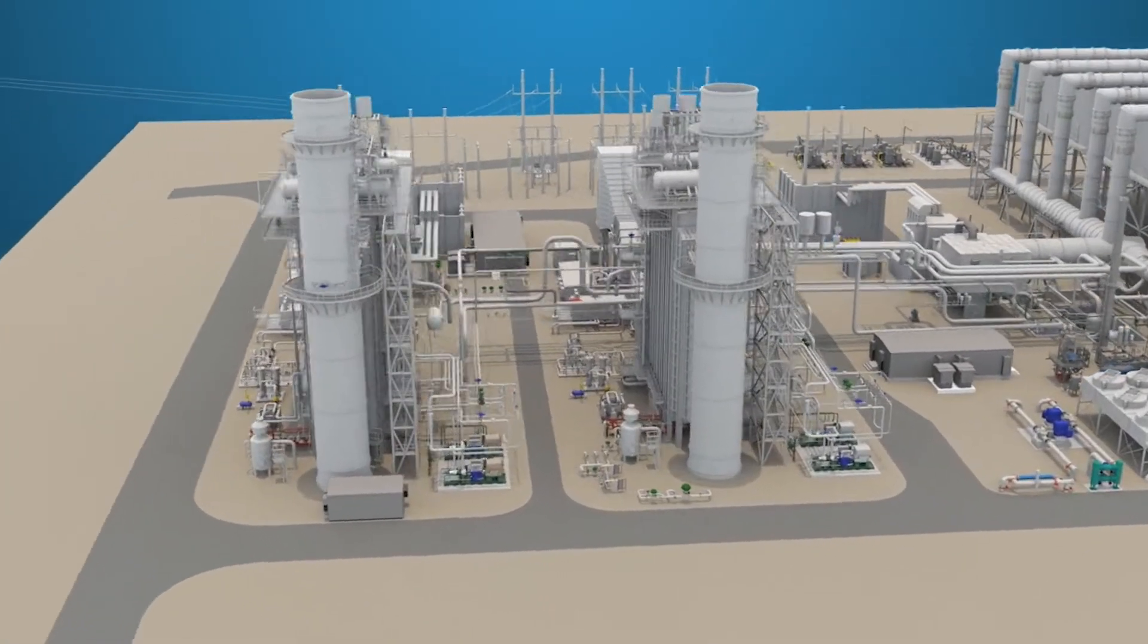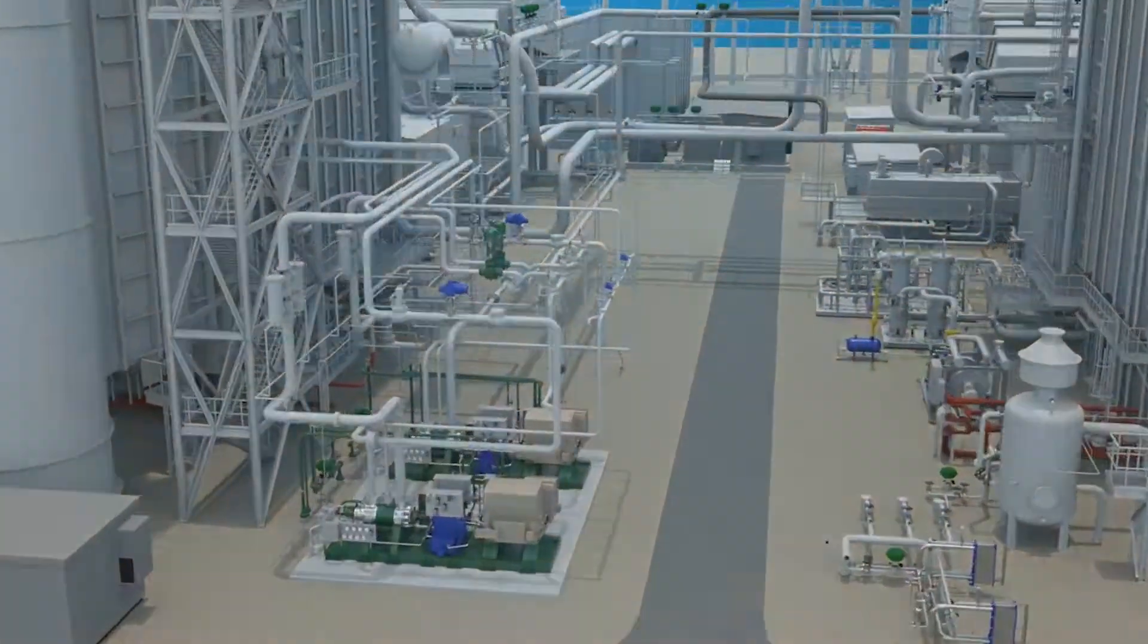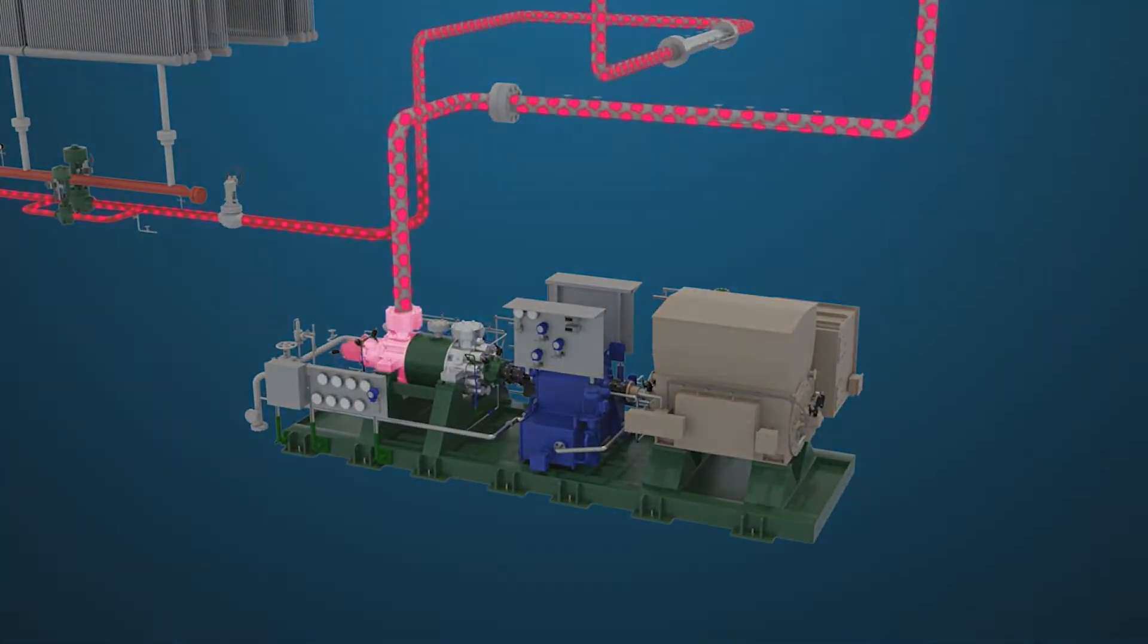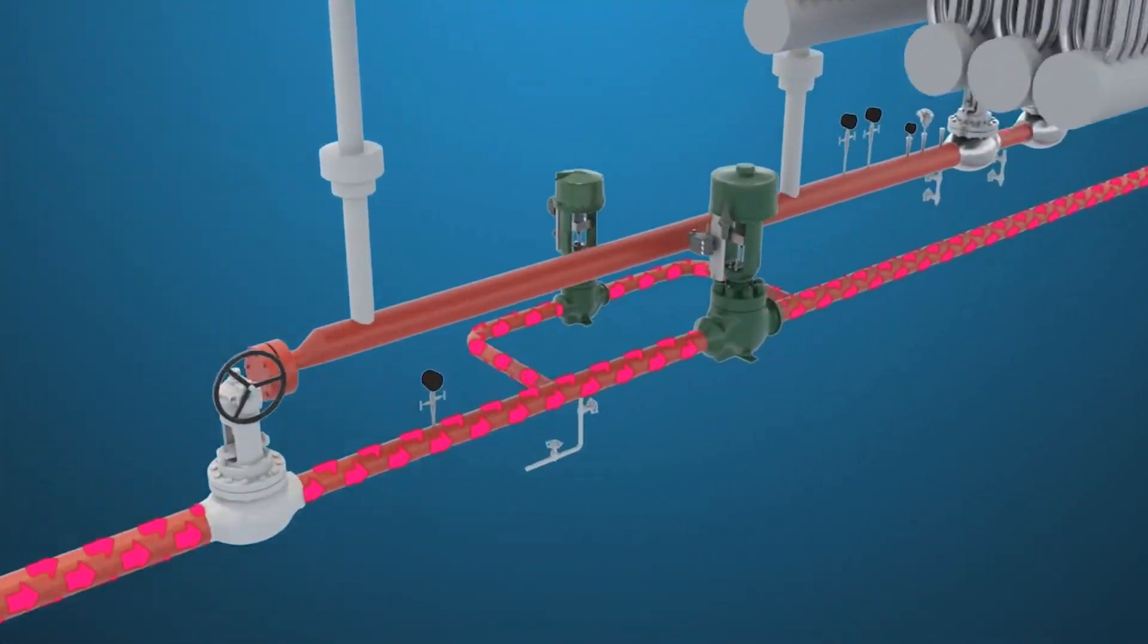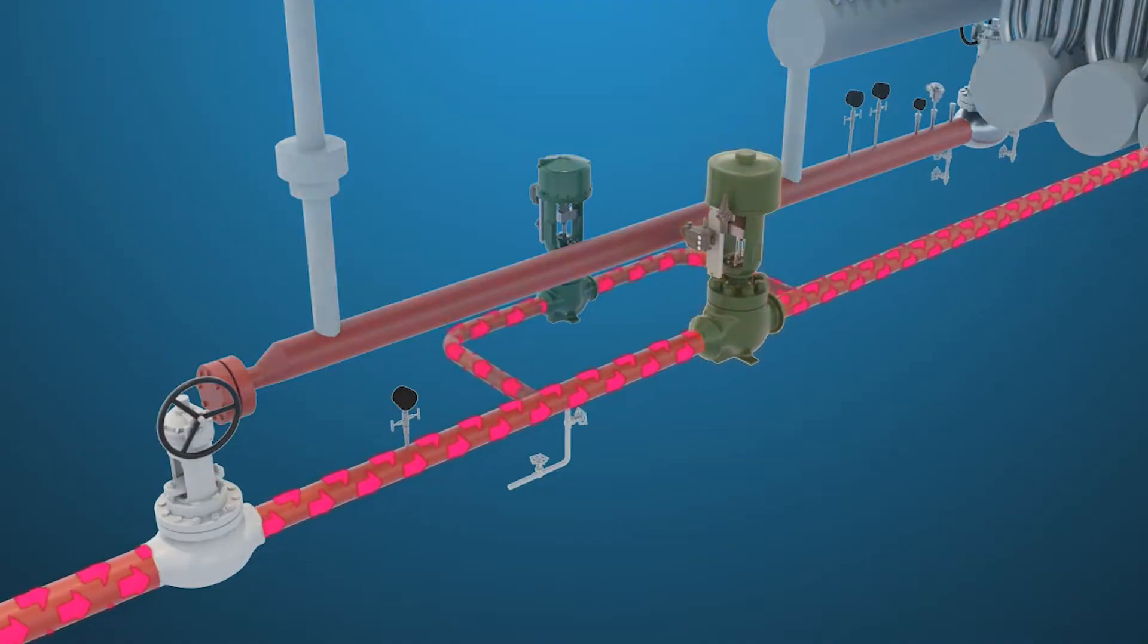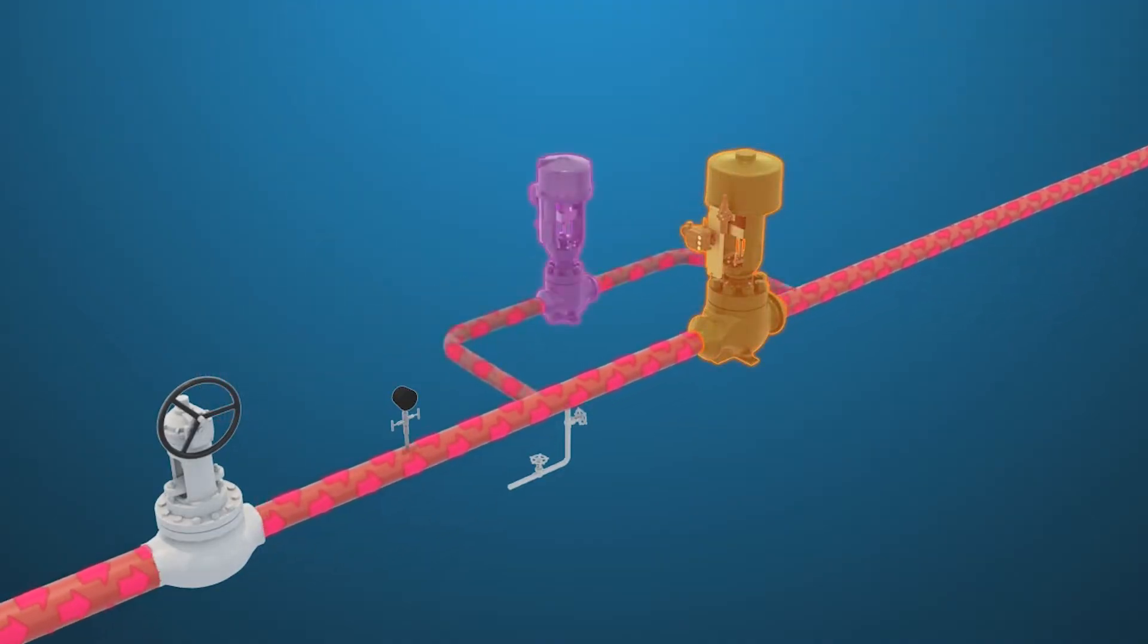The water supply for the high pressure or HP steam drum comes from the HP discharge of the boiler feed pump. Discharge flow from the high pressure stage of the boiler feed pump to the HP drum is controlled by a single or dual flow valve arrangement located upstream of the HP economizer.